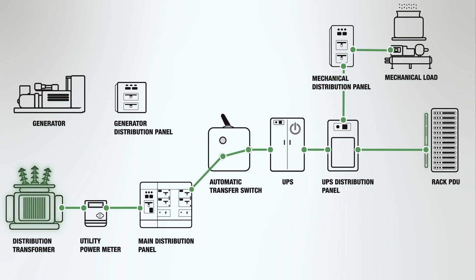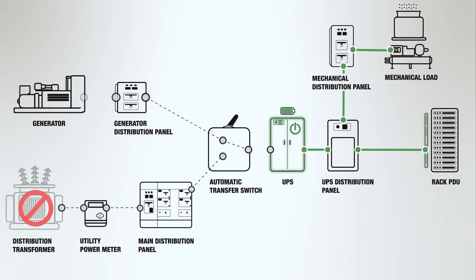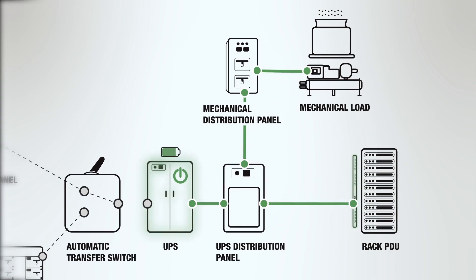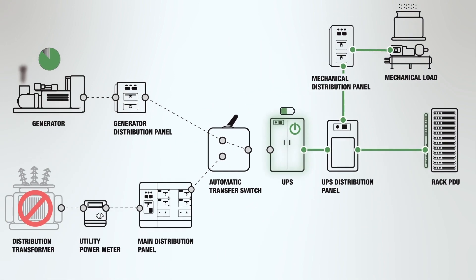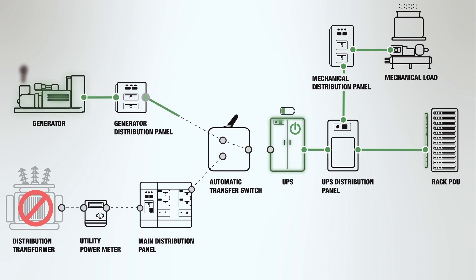This entire critical load is backed up from generators that are connected via the ATS. If the utility feed is interrupted, the ATS will send a signal to start the generators. It can take some time for the engines to power up. During this time, the UPS continues to use battery power to provide temporary power to critical equipment. Once the generators are fully operating and the ATS gear senses power with the correct frequency and voltage, the automatic transfer switch connects the generator to the circuit, allowing the UPS battery to come offline and charge in preparation for the next event.